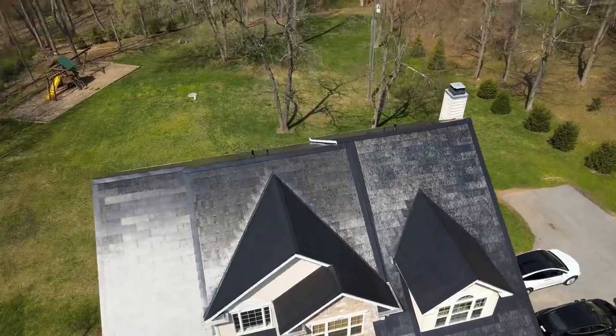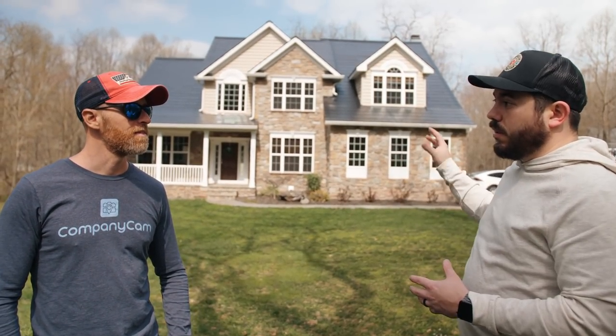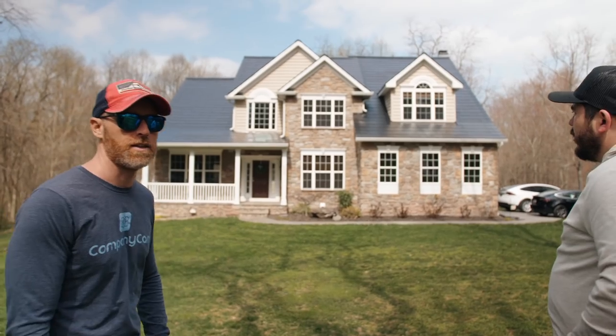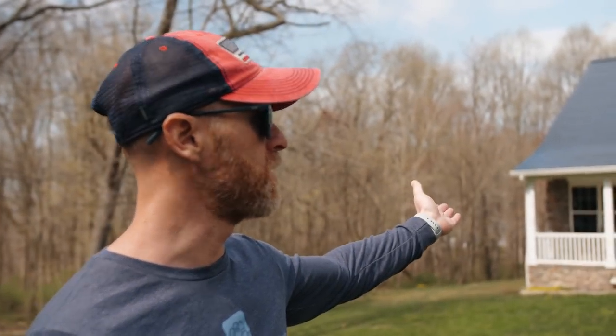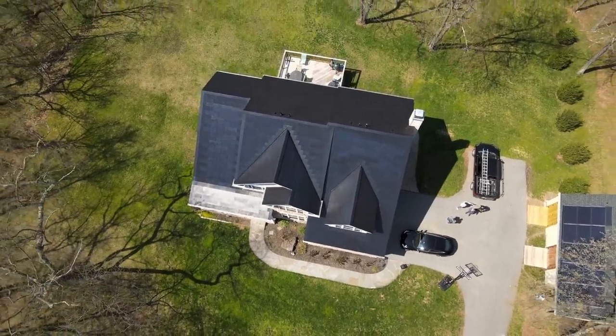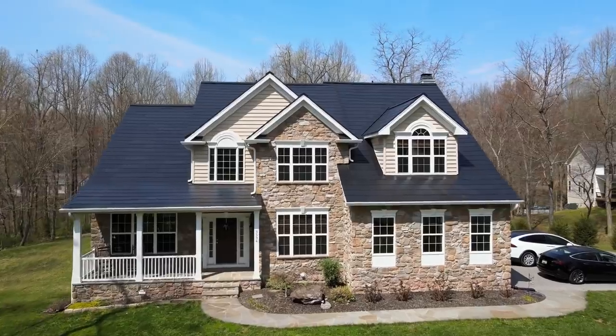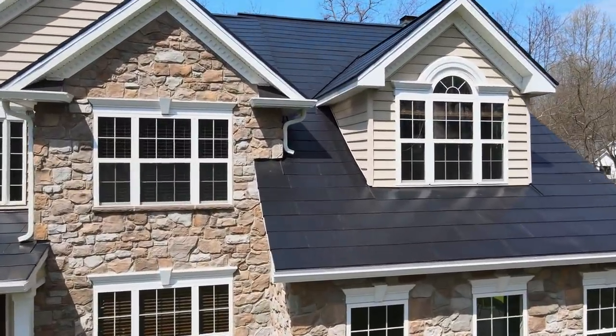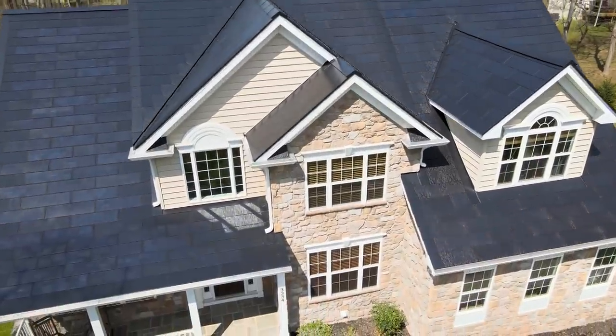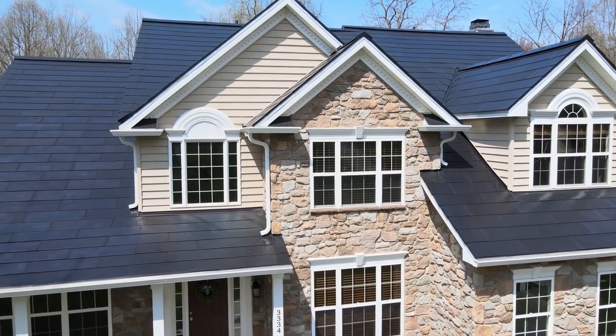This is what a completed Tesla roof looks like — it's beautiful. This is the Tesla solar roof fully installed. It was a few-month-long process between designing it and installation. Before you install the Tesla solar roof you have to consider the design and complexity. With my roof you have valleys, rakes, walls, undershots, aprons — this roof has just about everything. All of that has to be designed for, and the tiles have to fit perfectly on the mounting planes. We try to fit as many photovoltaic tiles as we can, but photovoltaic tiles cannot touch metal, so wherever there's an obstruction we put glass tiles around it with metal flashing.